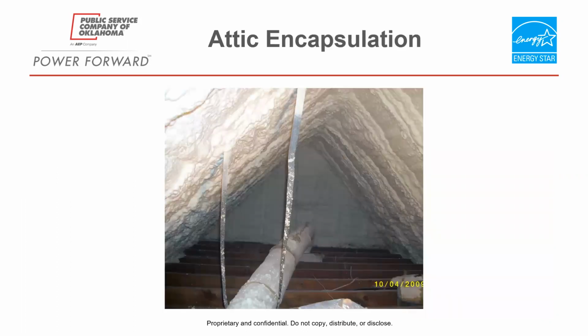This is yet another way to seal up and insulate an attic, called attic encapsulation. This is open cell foam, spray foam, a polyurethane based material, and they spray that on the roof deck. When you do this, you pull out all of the insulation inside so that the air barrier and the insulation are above the ductwork. That means that if there is a little bit of leakage on that ductwork, it's going inside the envelope instead of going outside the way it did in the previous picture. The other beauty of this is that a lot of times it will eliminate really high temperatures up in the attic, usually about a 5 degree temperature difference between the inside of the house and the attic. So it saves a tremendous amount of money.